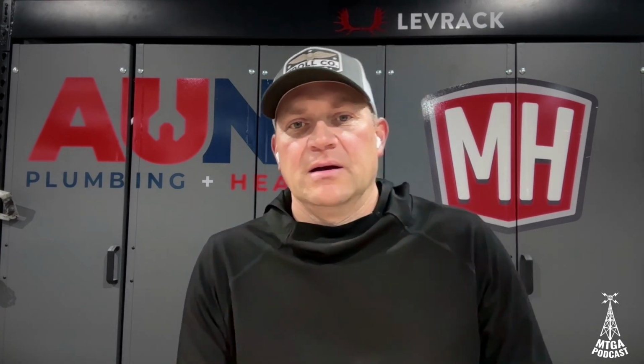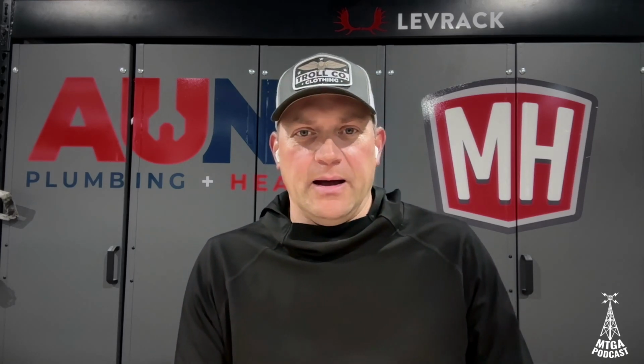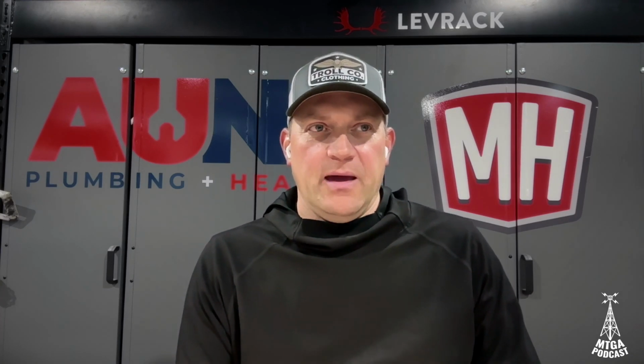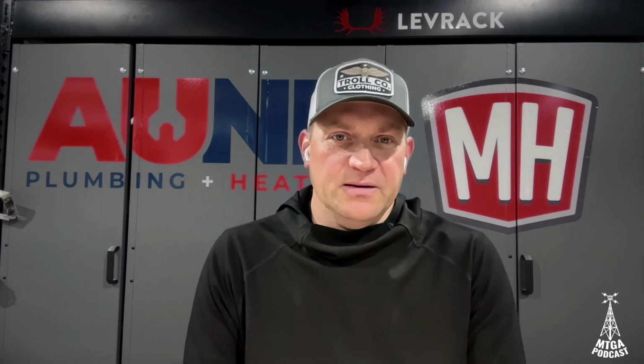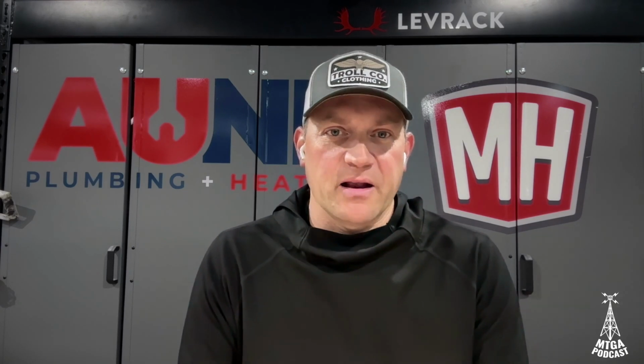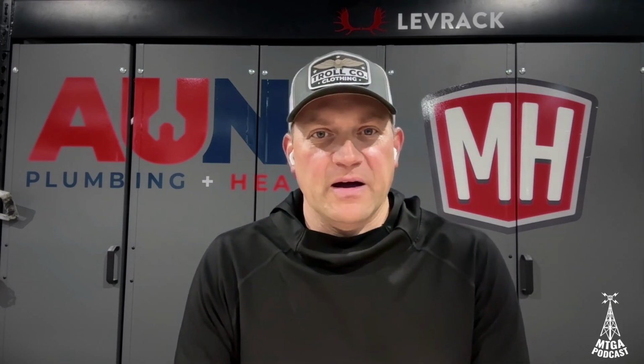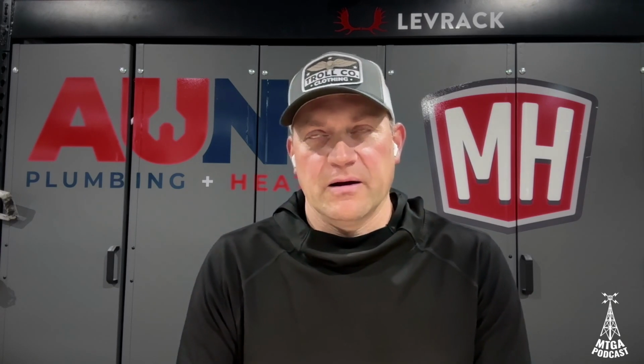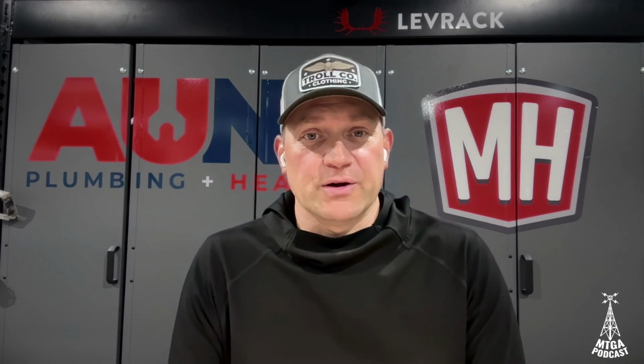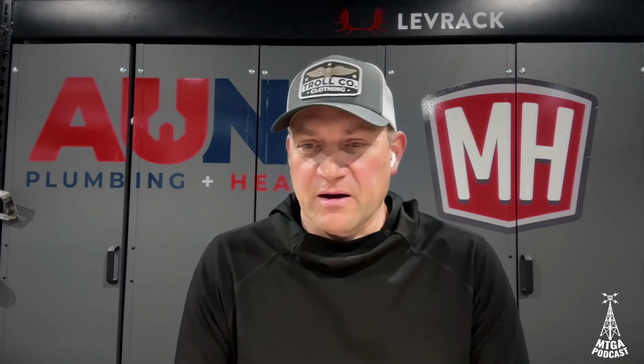communicate via Modbus, which is nice in the sense that there's a lot of information passed back and forth. And it's kind of cool on the control panel inside. You're able to dial through that control and see supply and return temperatures in and out of the monoblock. You're able to see EEV valve position. You're able to see supply or discharge pressure and temperature, suction pressure and temperature, liquid line pressure and temperature.